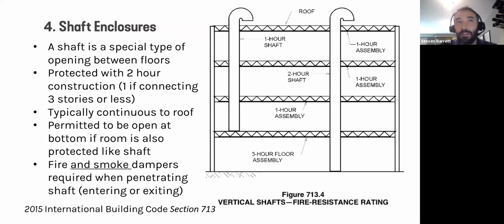So you are all probably familiar with running your ducts through shafts. And the typical requirement is for a 2 hour rating of shafts. It is only 1 hour if connecting 3 stories or less. And shafts are typically continuous to the roof. They typically start at the slab and go all the way up to the roof, but they are permitted to be open to a room that is of similar use to the shaft and protected like a shaft. So it could open directly into a mechanical room.